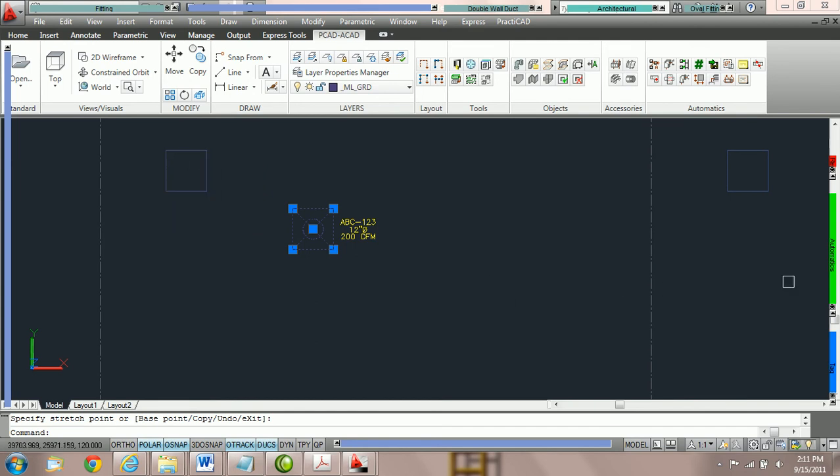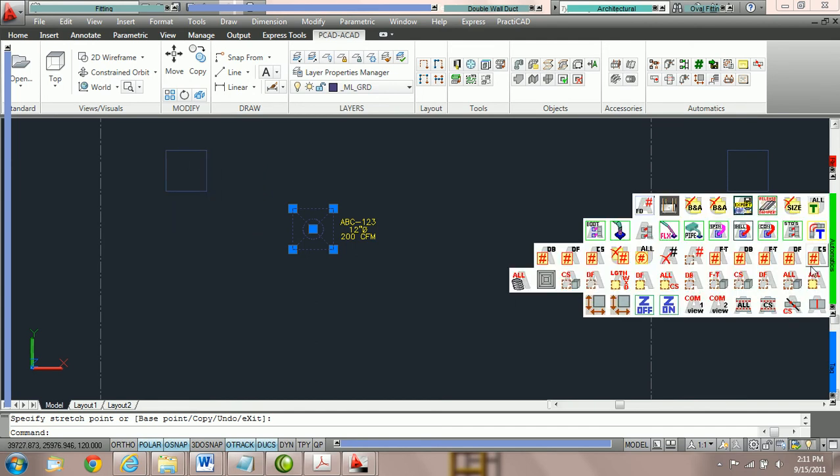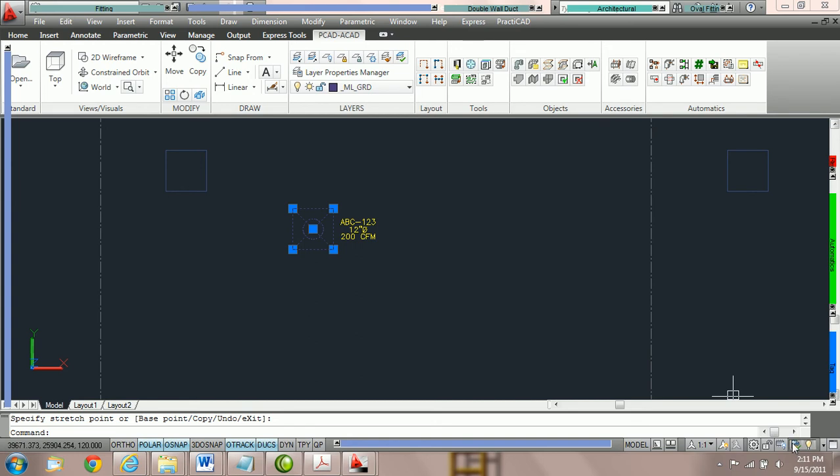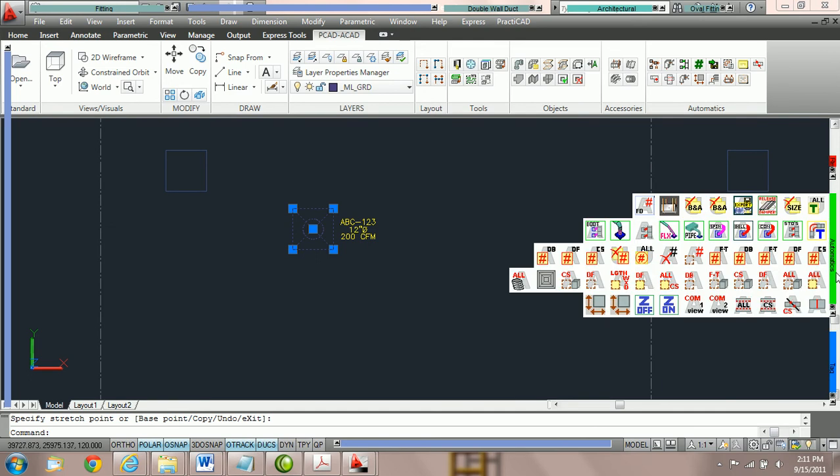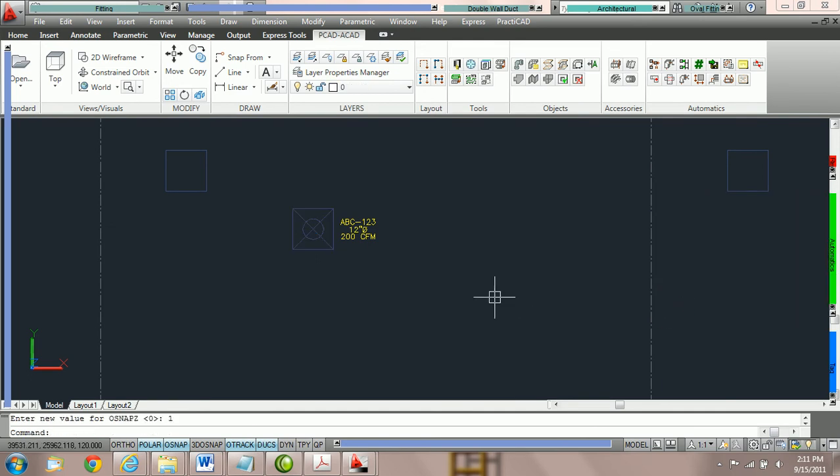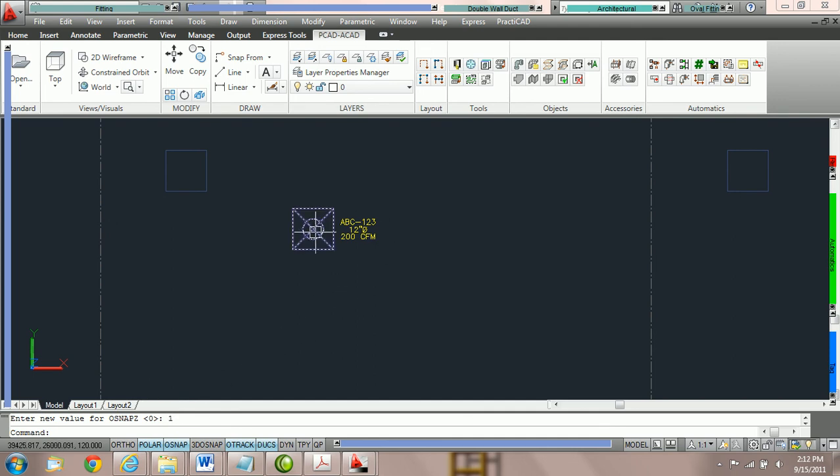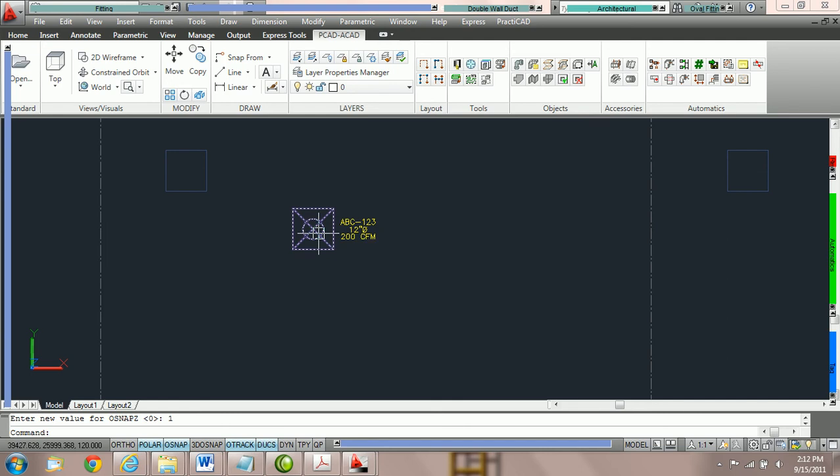So what we want to do is go into your automatic bin and click your replace Z on automatic. If you're using AutoCAD MEP, you should have an icon for Z on in the bottom right-hand side of your screen, about where my cursor is now. But in this exercise, we're going to click Z on. Once you do it, make sure it should say in your command line, enter new value for osnap Z, zero, one. That means that we've got replace Z on. This means that no matter where we copy this grill right now, PractiCAD or AutoCAD are not going to change the elevation.